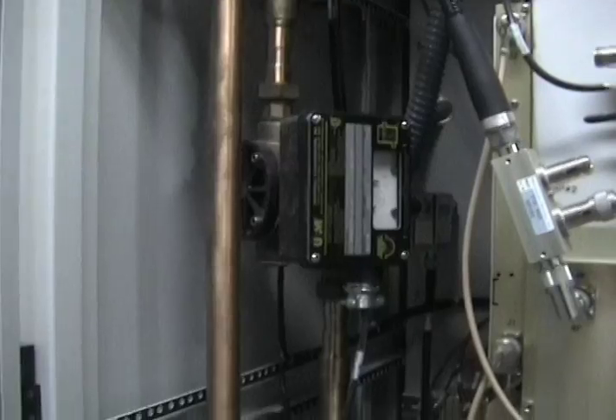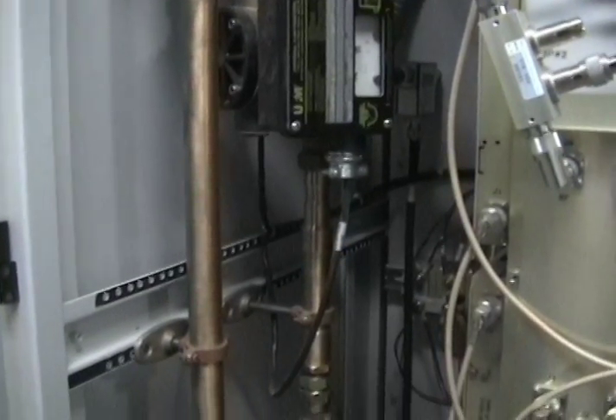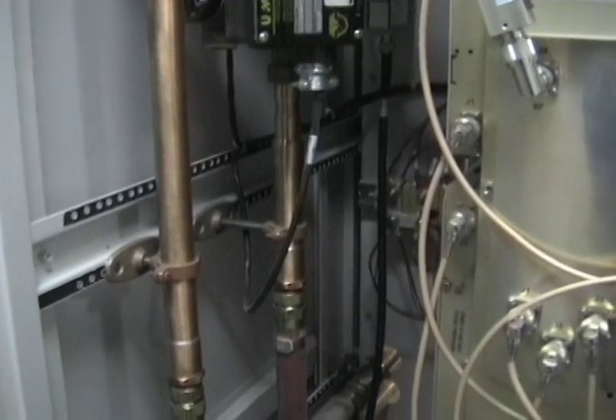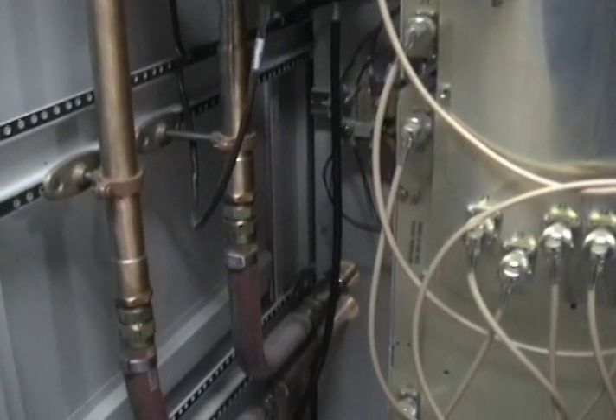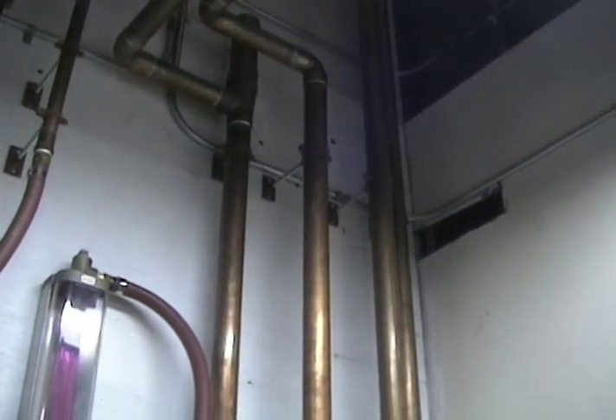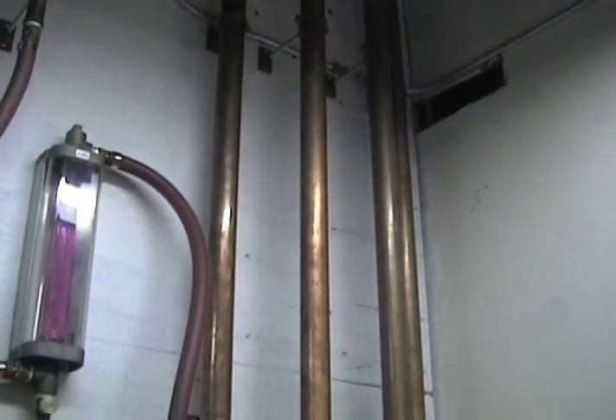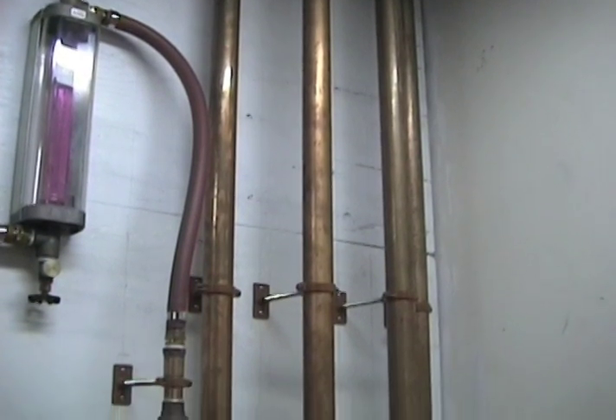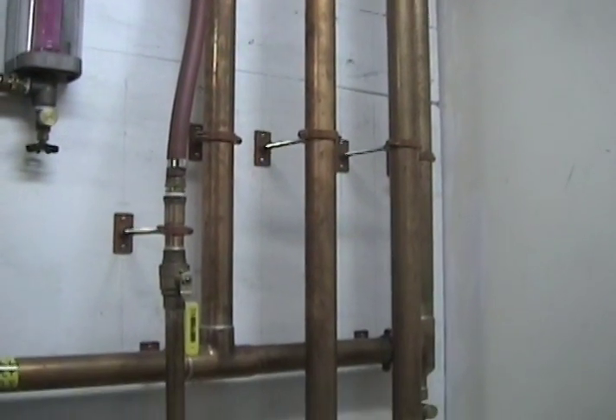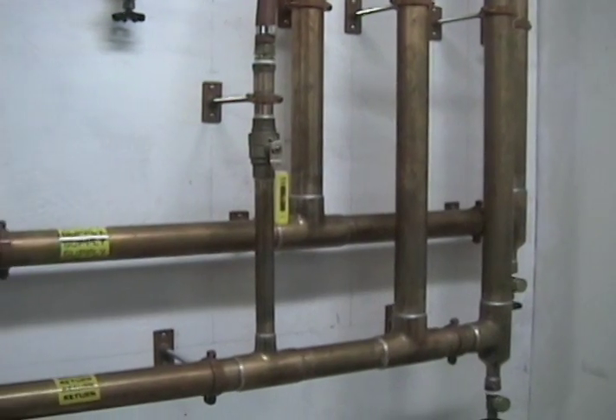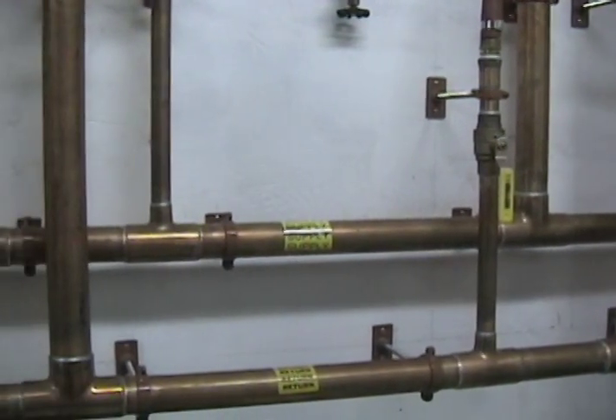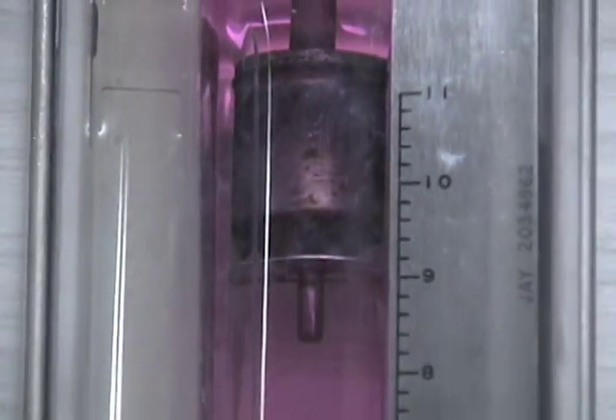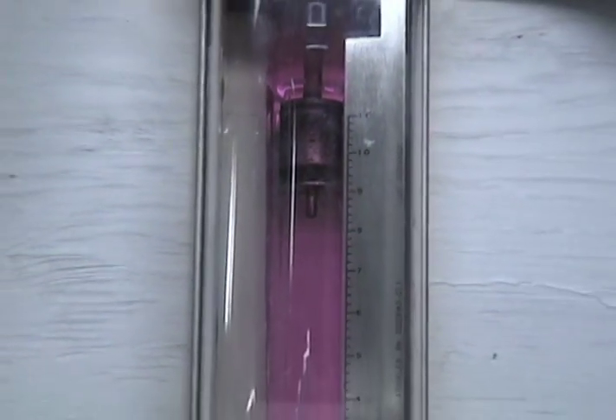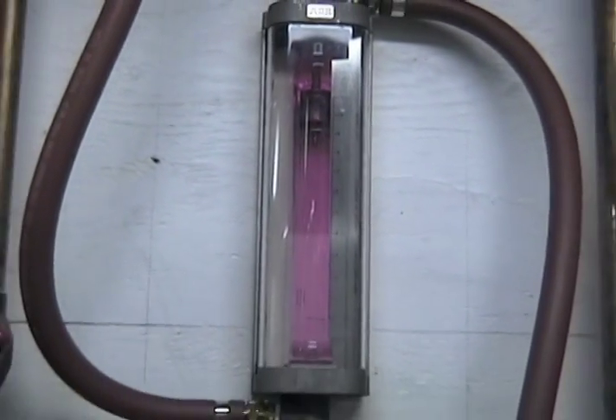Cooling of the IOT is monitored here, where the temperature and flow of the coolant can be observed as it returns from the IOT. On the back wall behind the transmitter is the plumbing system for the coolant. Pipes from the heat exchanger on the roof come down and are distributed to the HPAs and the dummy load. The flow of coolant to the dummy load is monitored precisely in order to perform power calibrations on the transmitter.